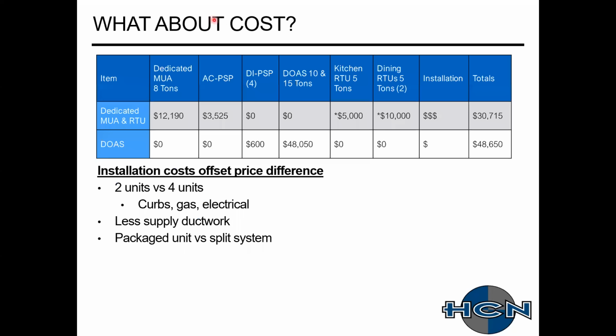So what about costs? That's typically when people start hearing dedicated outdoor air units, they're like, oh, this could be very costly. Installation is really the biggest key here, depending on where you are. For this example in Tennessee, the installation cost difference was right around 13 or 14,000, with the DOAS being a little bit cheaper to install. So once you added those numbers in, it came pretty close to being equivalent pricing.